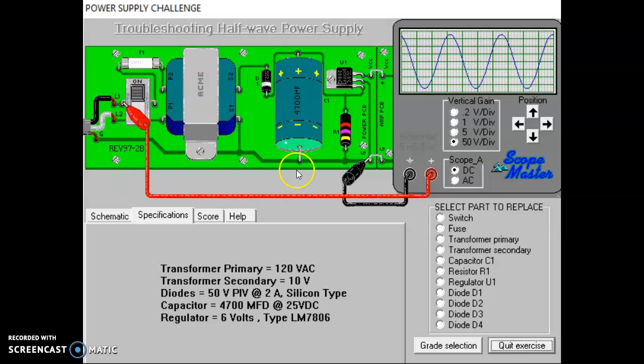So that's where we're going to start. Here's our line voltage going in, and notice on the AC or the DC sense you end up with the same waveform, no change here. We're at 50 volts to the division. That's because our input is probably around 330. If you take the peak-to-peak voltage from a 120 RMS, you're going to be just shy of 340 volts coming into that. If you look here, counting squares: 5, 10, 15, 20, 25, 30, that's 300, plus about half a square either way, so we're just shy of 350. We're probably about 340 volts, which makes sense with our calculations from peak to peak. So no real worries here.